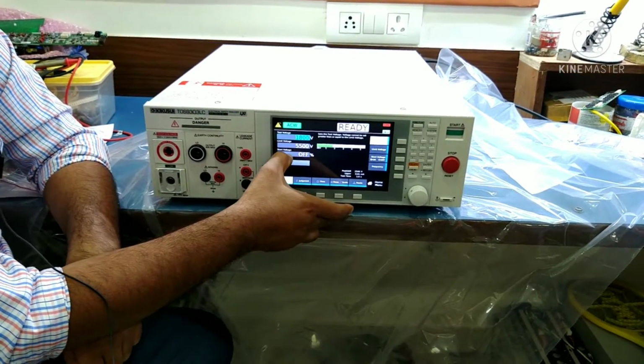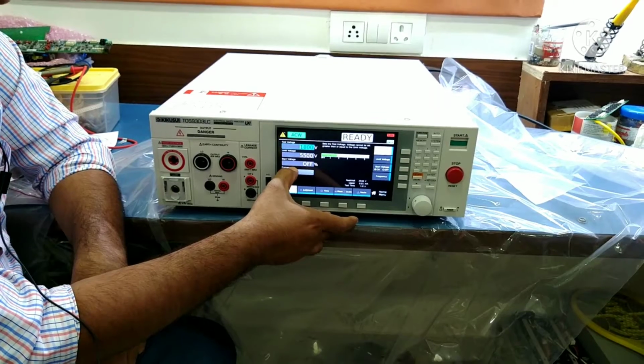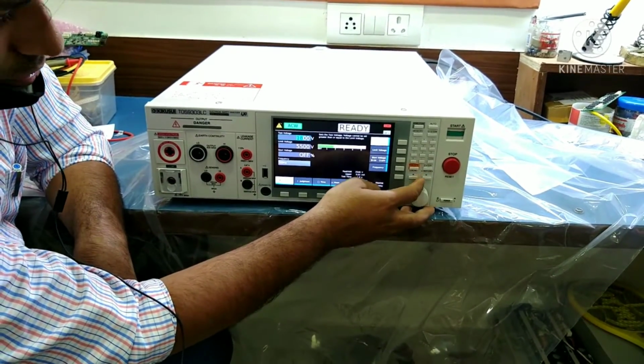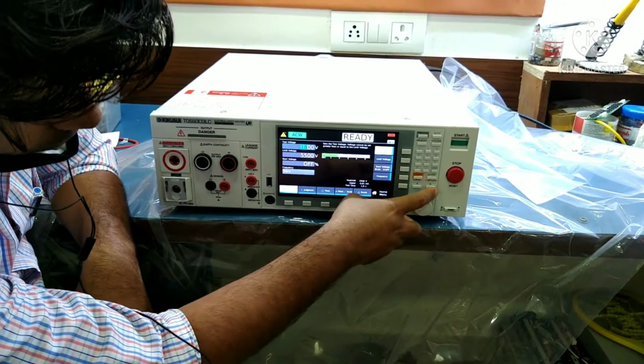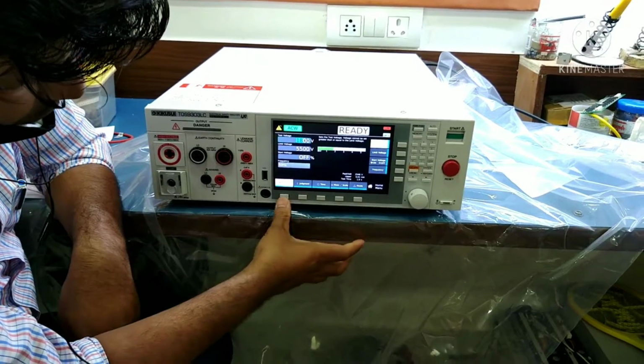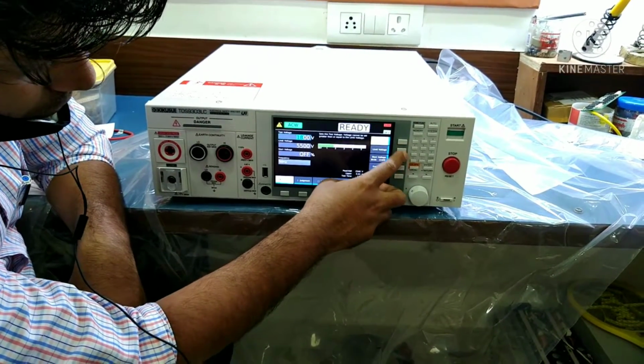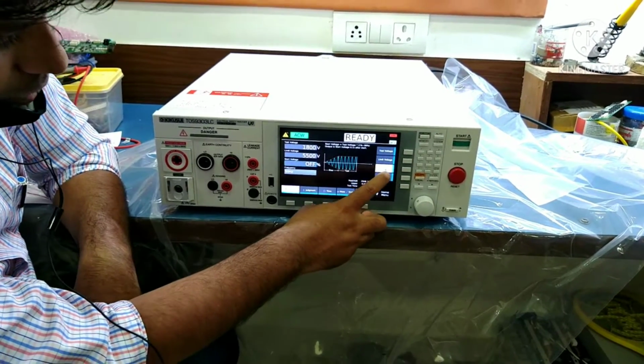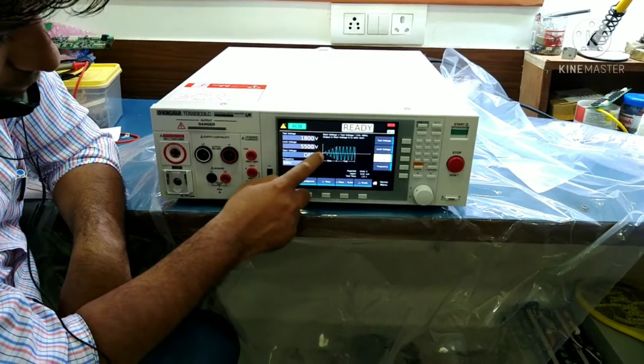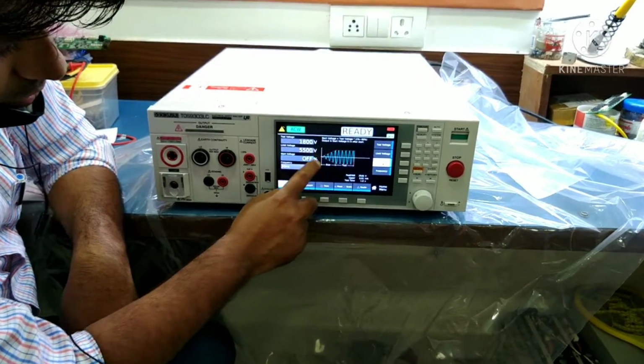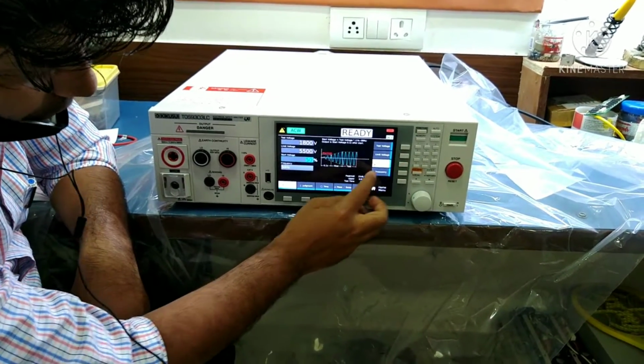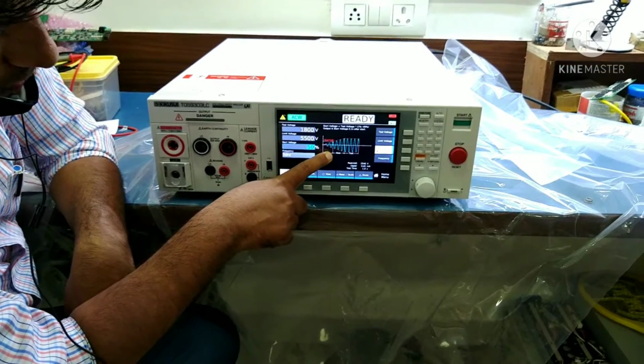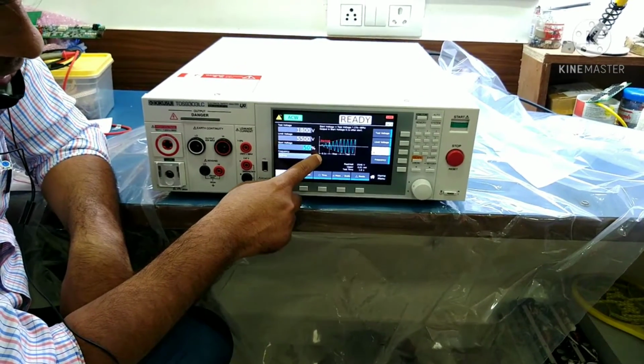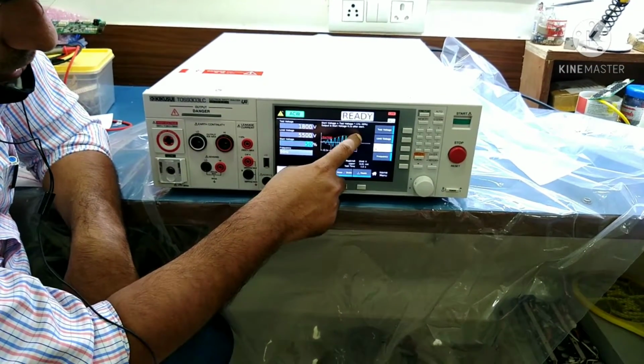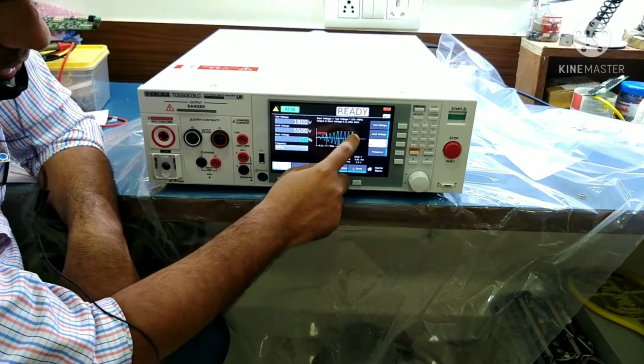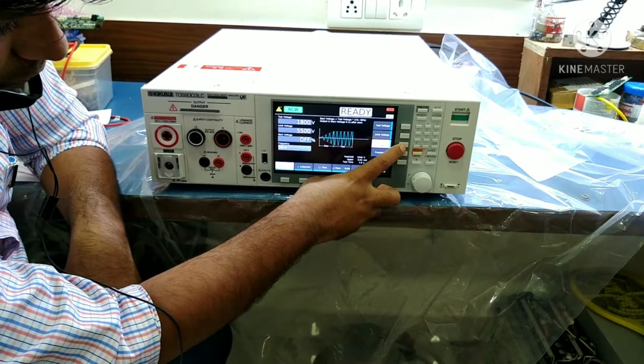This is the start voltage. Basically the start voltage is off. If you want the start voltage at 50%, you can turn it on. With the start voltage off, the voltage will rise this way, like that. So you can make it on or off. If you turn it on, you can set the voltage, for example 50%, and the voltage will rise at a 0.1 speed. Again, it will start according to your test timer. By default, I am going to keep it off.